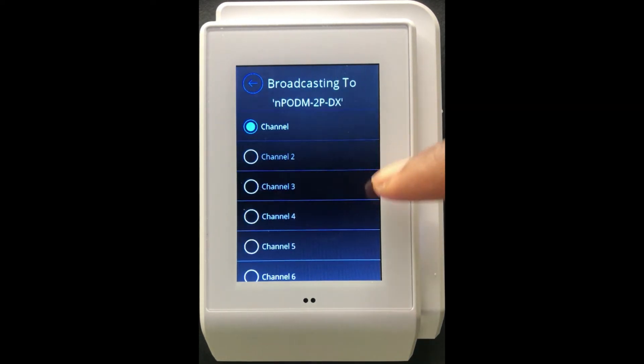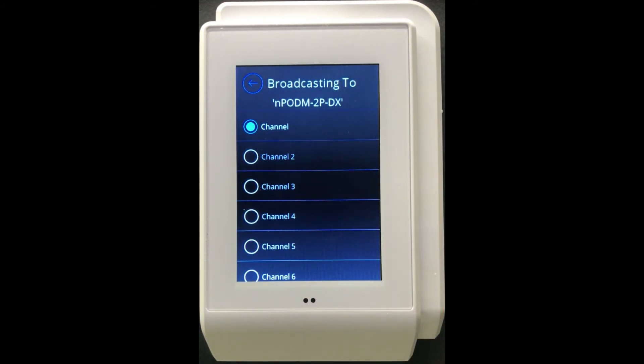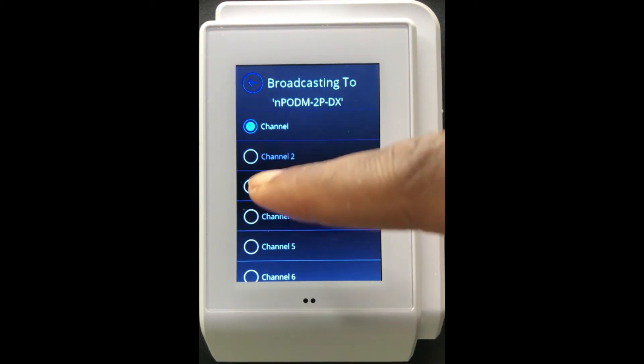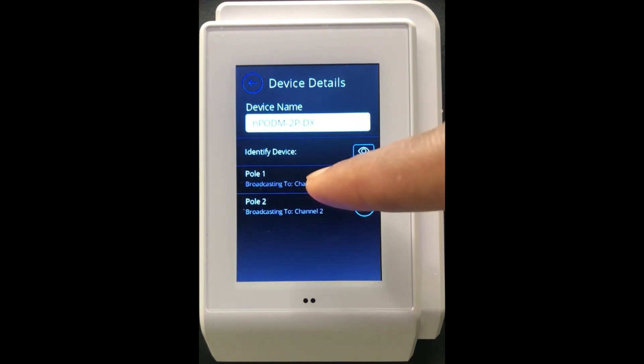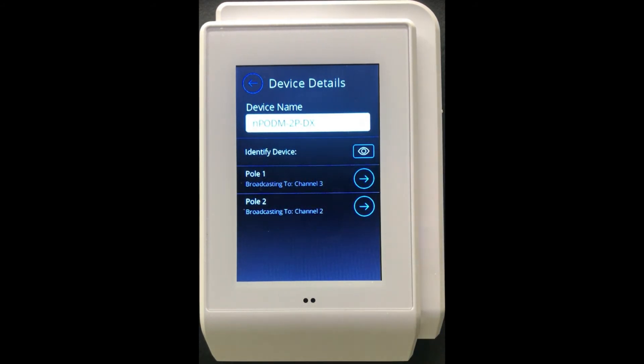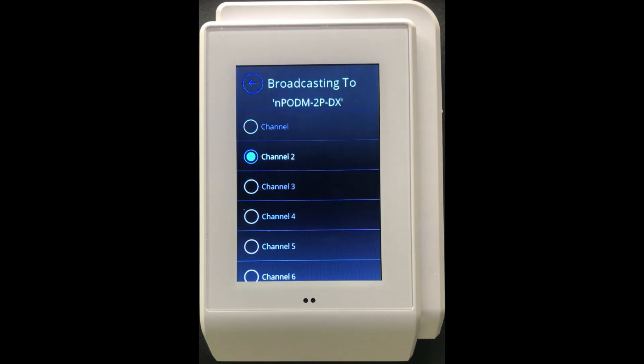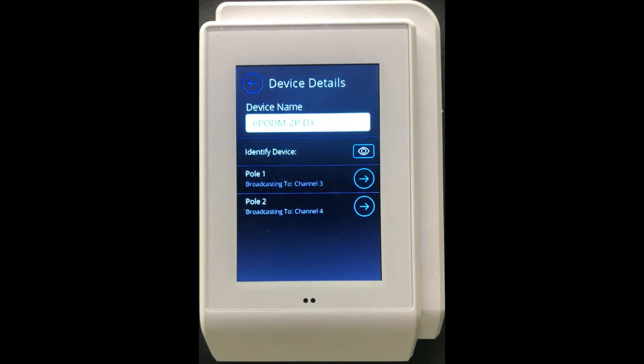If I modify the first pole of this switch, I can select any one of the 16 local channels available on this NDTC. Right now it's associated to channel one, but let's say I want it associated to channel three — by selecting channel three, this pole will now broadcast specifically to channel three. I can make the same modification for the second pole and associate it to channel four.